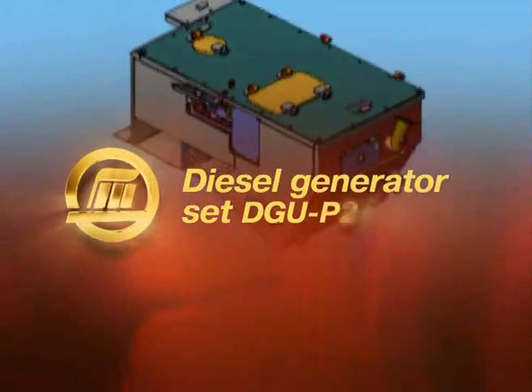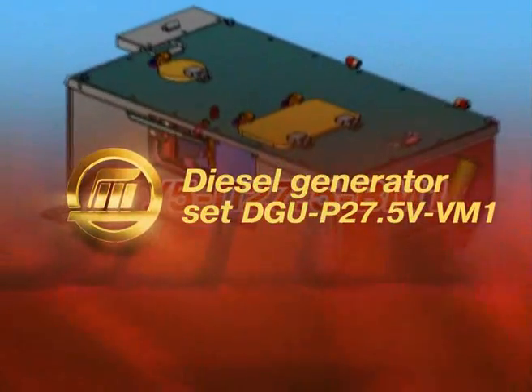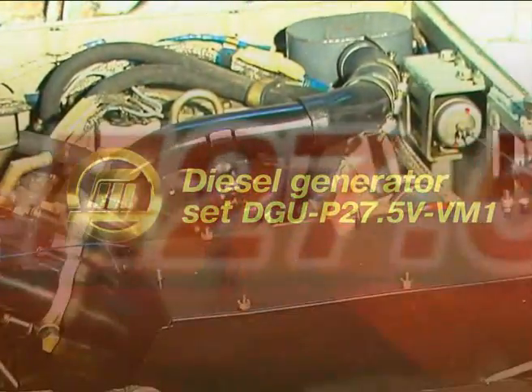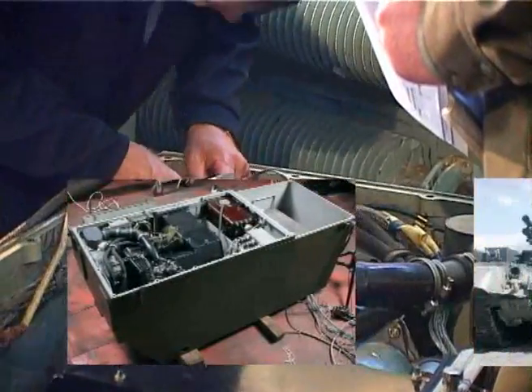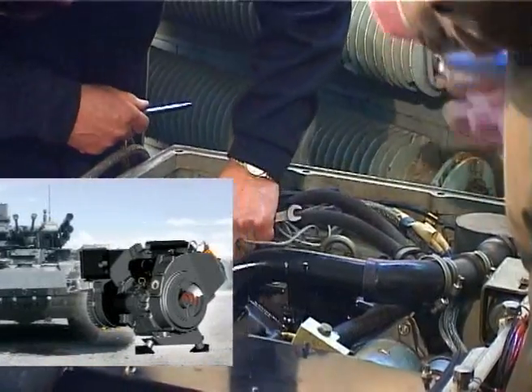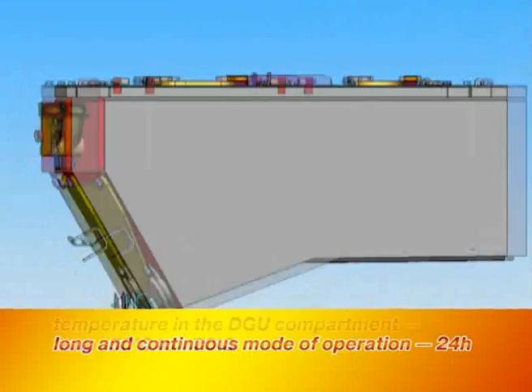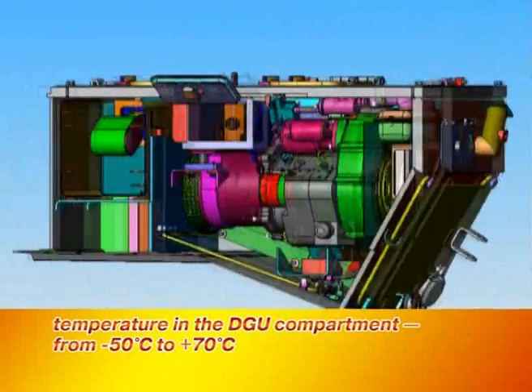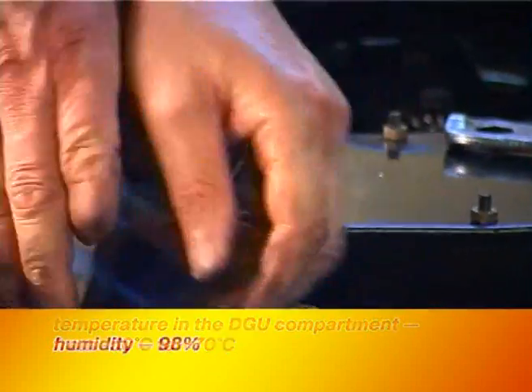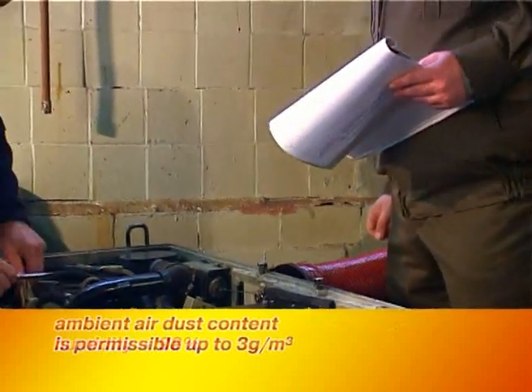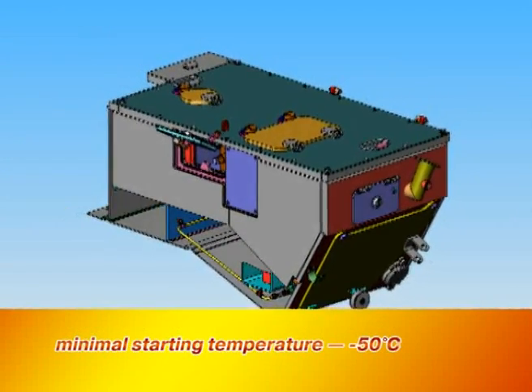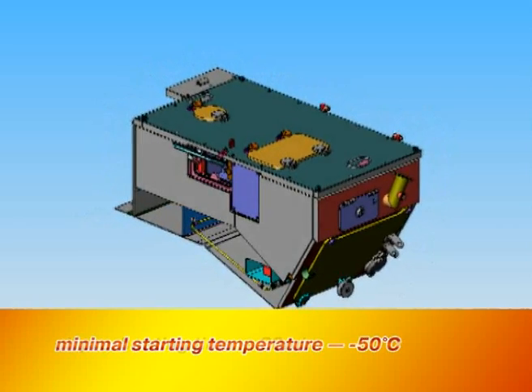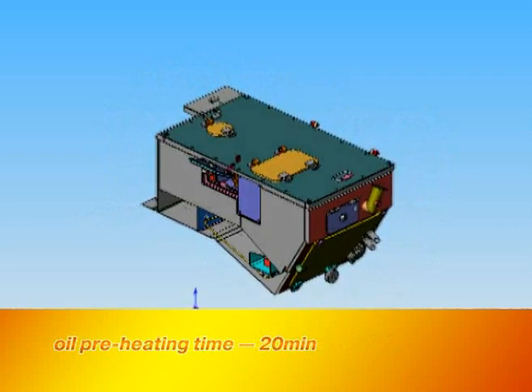Diesel generator set DGU-P27.5V-VM1 is designed for use as a basic or reserve on-board power supply for various military purpose vehicles and equipment, with capability of working in the closed space of an armored compartment. The diesel generator set provides long, not less than 24 hours, continuous mode of operation. Permissible temperature in the DGU compartment is from -50 to +70 Celsius degrees. Humidity 98%. Ambient air dust content is permissible up to 3 grams per cubic meter. Minimal starting temperature with use of the built-in pre-start heating system is -50 Celsius degrees. Oil preheating time is no more than 20 minutes.